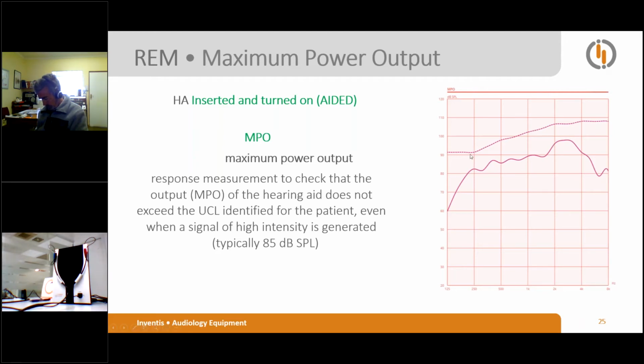So, this continuous curve is the curve the MPO acquired for the patient. The dashed curve is the one provided by the fitting rule. So the patient who wears that hearing aid, the patient who has that pure tone audiometry, and whose hearing aid has those specific characteristics, must have this maximum power output, which does not exceed the dashed line.